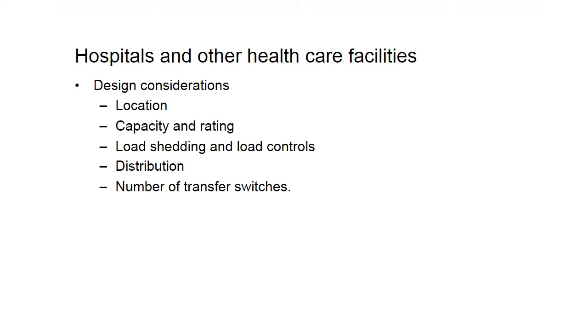to be designed with selective coordination. The key here is to isolate the faults and maintain operations to the balance of the facility. So if you do have an issue, you want to keep it as local as you can to the problem at hand.